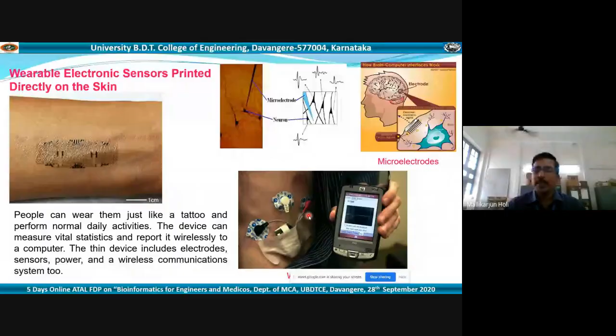Sometimes, if you go back to the previous slide, you can see the electrodes are connected to the human body, and through wires they are connected to the machine. In this case, the patient becomes immobile. He cannot move. At that time he should be connected to the bed, or to the machine. To overcome these difficulties, nowadays we have wireless electrodes. These are the electrodes you see here. These electrodes are mounted; they have a processor and a wireless transmitter which transmits the signal from the body to the device, which may be mobile. Through wireless, the subject is free to move from one point to another, and you cannot restrict his movements. When you go wireless, during routine activities also the data can be captured, and through wireless media we can transmit it to the hospital or the doctor's gadget. It may be a laptop, a desktop, or a mobile. Such advances are happening in the field of biomedical engineering.